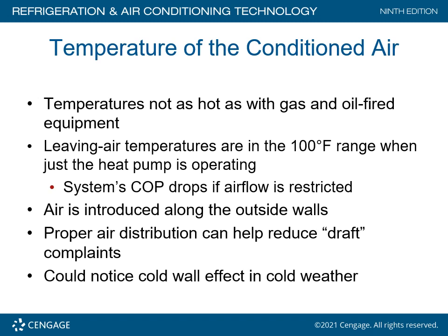The system's COP drops if the airflow is restricted. This is a big deal. We'll talk more about this. Heat pumps are very unforgiving if you have a restricted air supply or inadequate returns. Air is introduced along the outside walls. Proper air distribution can reduce the draft complaints.